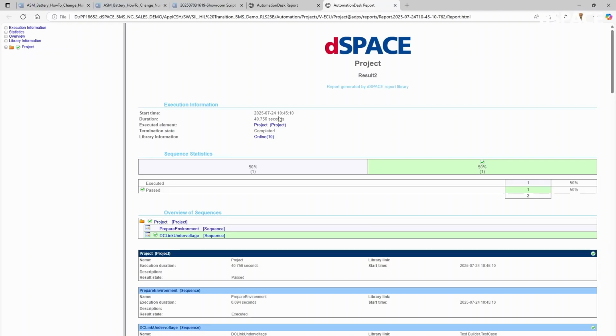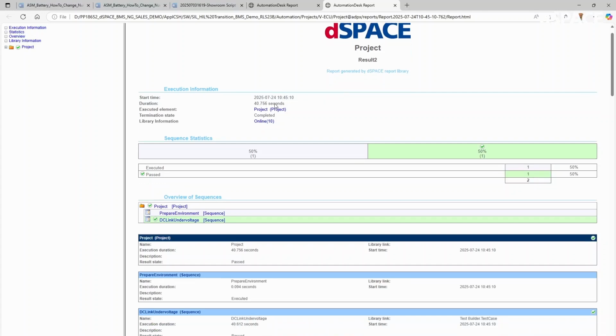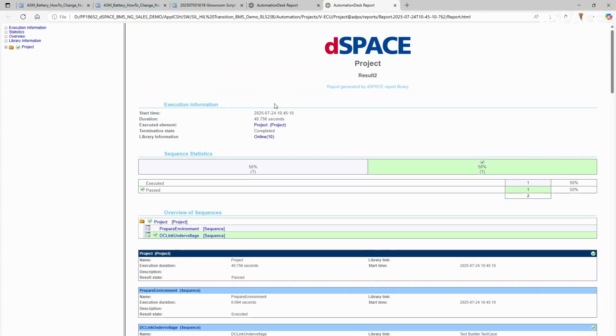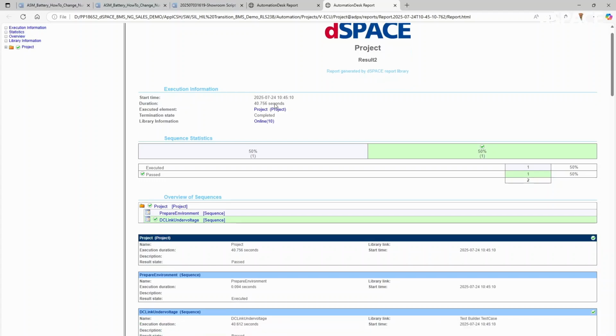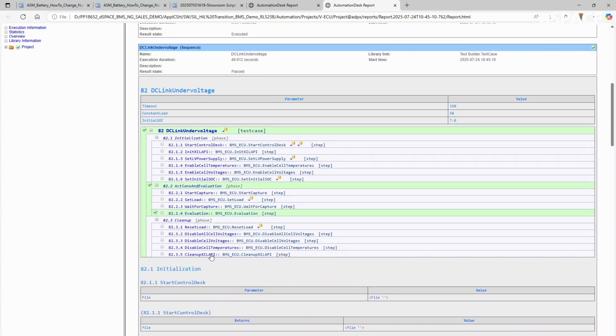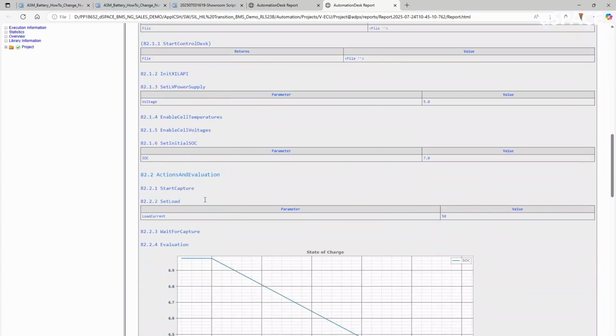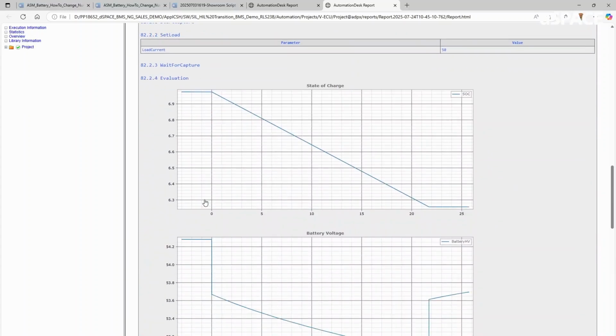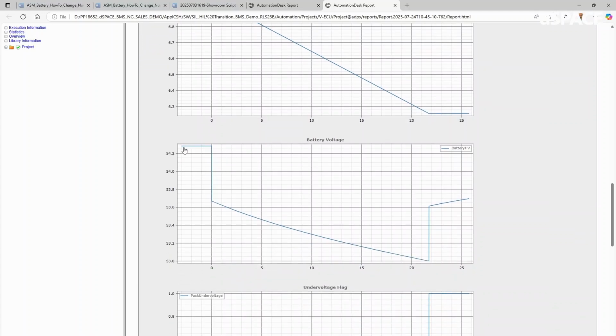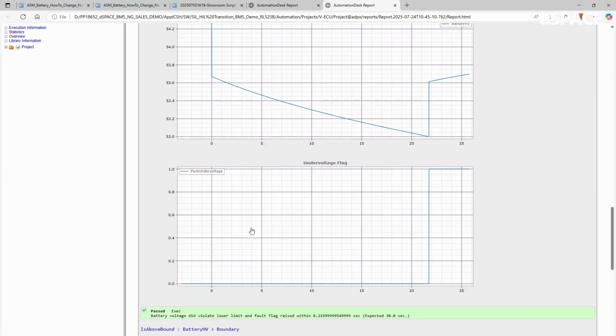Opening a report, you can see what has happened and what were the steps performed during the test case. Here a description of the different test cases is given, but more interesting are the graphs that are drawn. One is the state of charge, which is starting at 7% and going down. Also the overall pack battery voltage is having a drop here in the beginning because the load is connected, and then it's further going down. And most interesting is the undervoltage flag, which is raised by the ECU, which is drawn at a certain level at 53 volts.